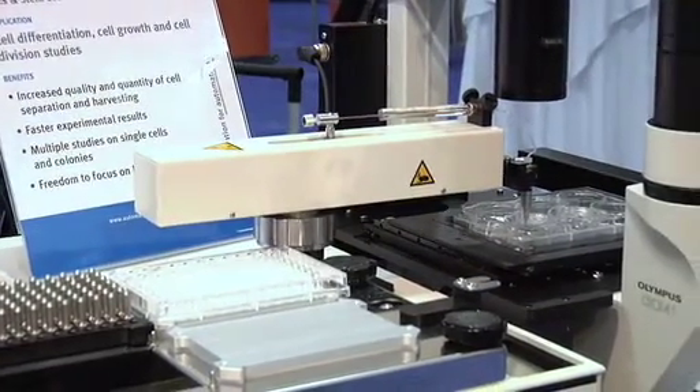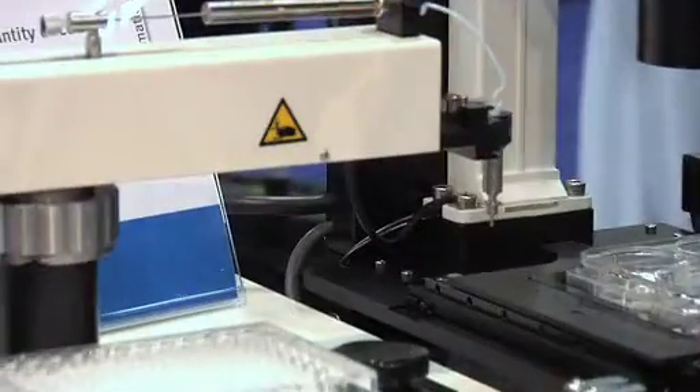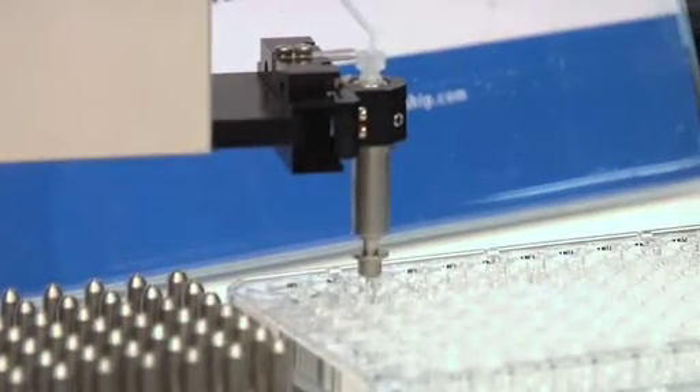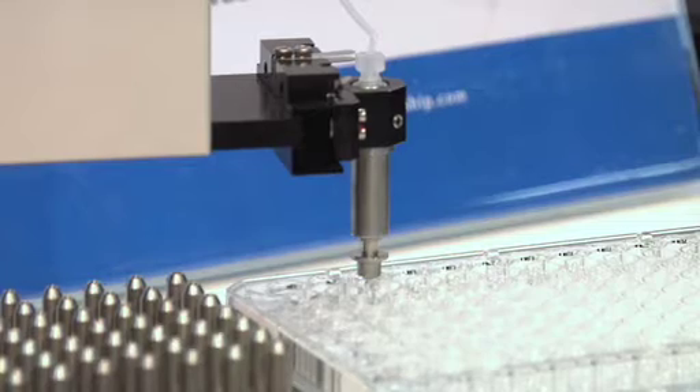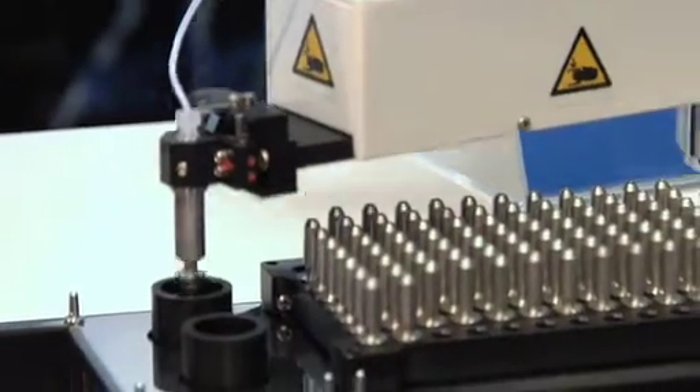At this point we're picking anywhere from 400 to 600 micron beads with an 800 micron tip. The tip will do a scrape motion in a crosshair. We also have a glass capillary that will go all the way down to 50 micron, so you could be picking single cells and things that would not be fully confluent — you could pick as low as single cells, parts of a colony, or the colony itself.